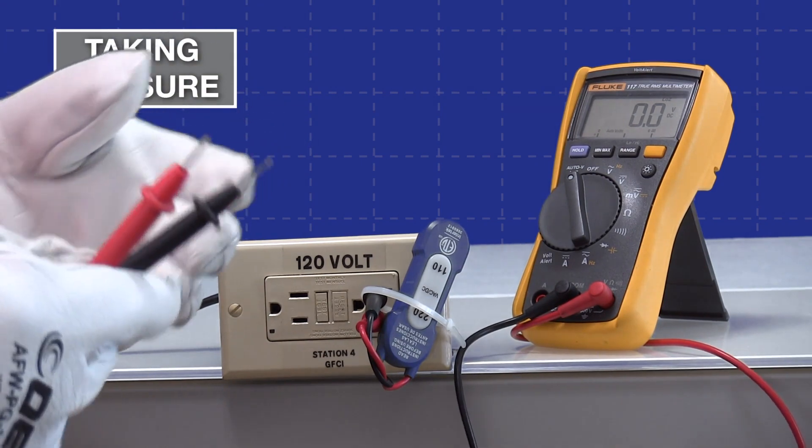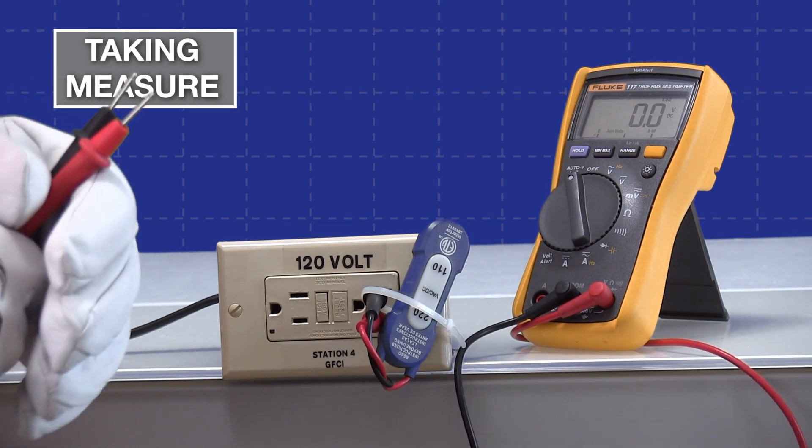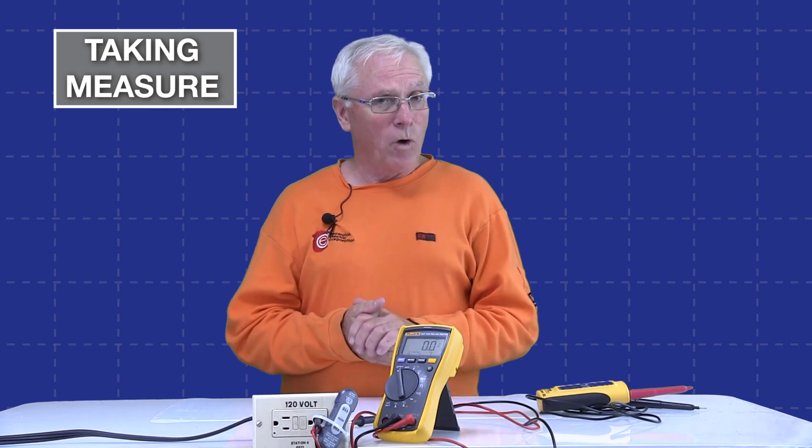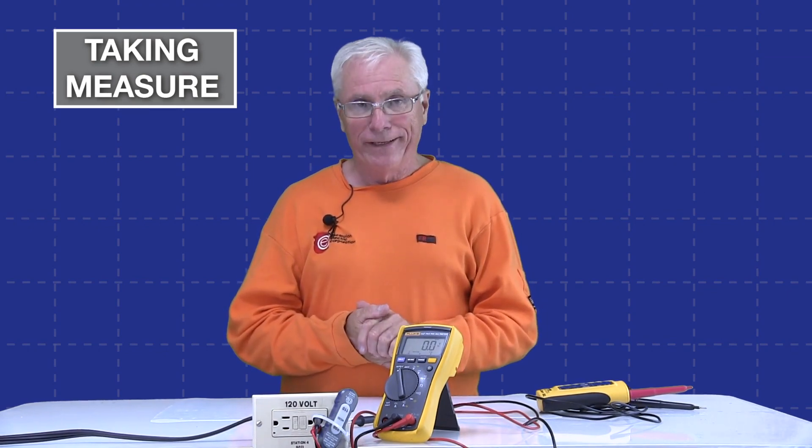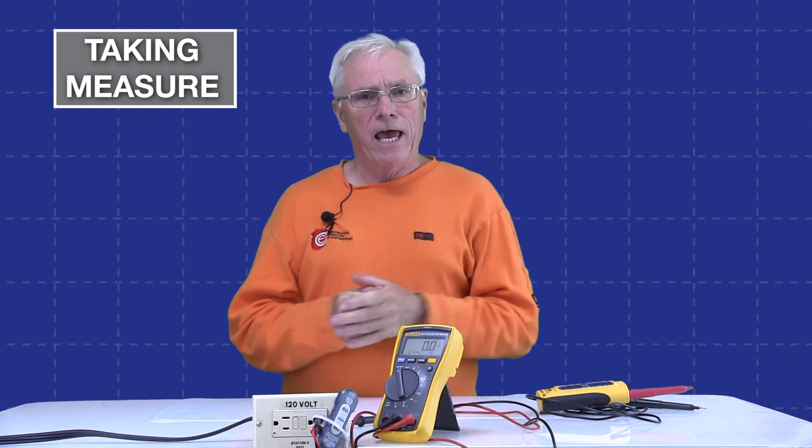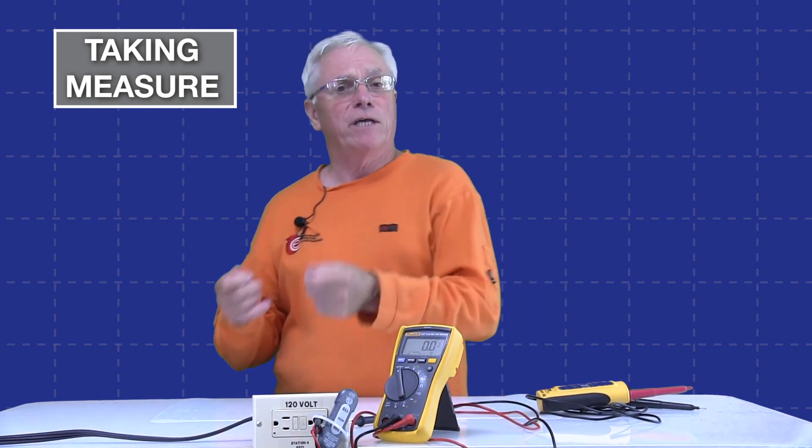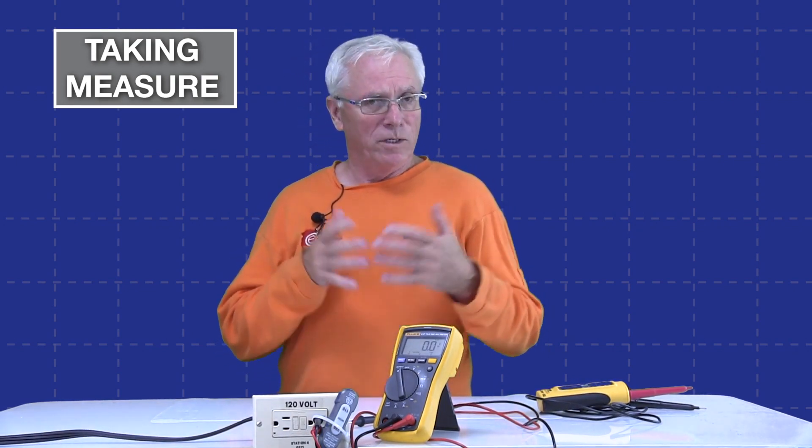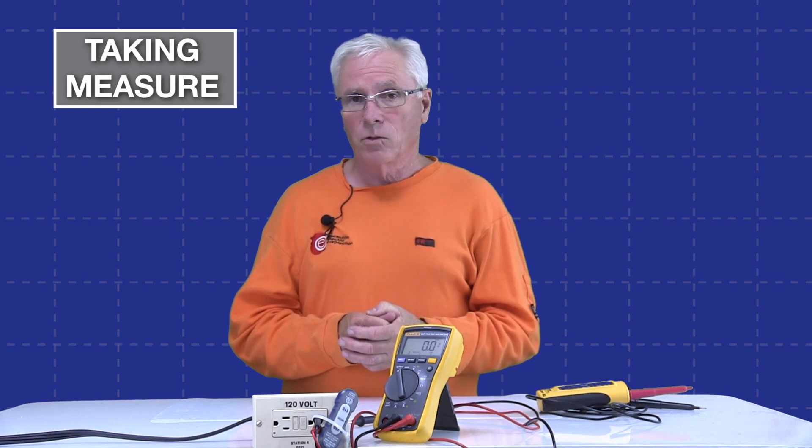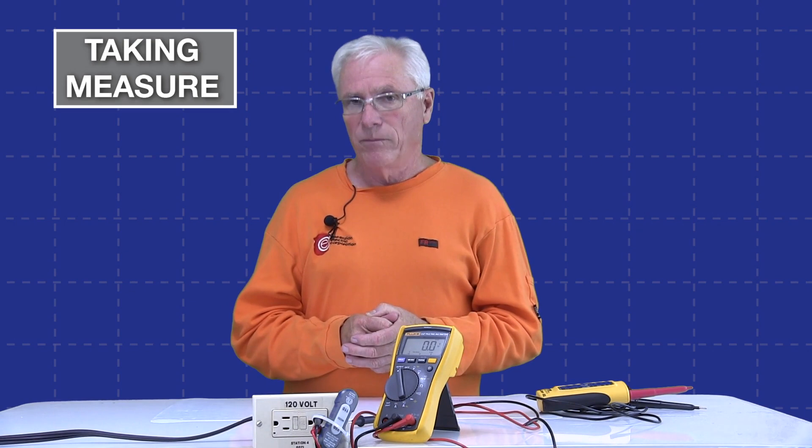In order to solve that problem, we started making devices with high impedance input, but that created another problem called ghost voltage, and our next lab we'll take a look at that. Thank you so much for watching our video on meter loading. One thing I didn't mention, when I was an apprentice is the first time I ran into that, and I didn't understand why sometimes I could take a measurement to ground on a GFCI receptacle, and sometimes I couldn't. I didn't realize it was the difference between the two meters. As I mentioned previously, in our next video, we're going to take a look at ghost voltage, which is another really interesting problem.